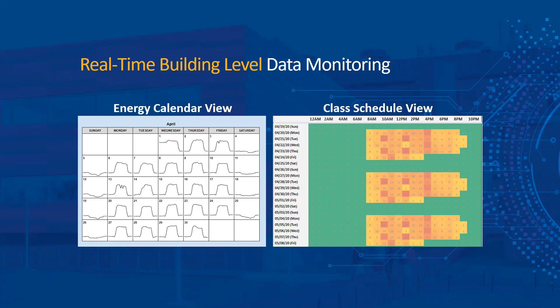So with all these buildings that we have in our system, it's almost impossible for 2 people to go through every single one every day. So what we did was we baselined the buildings. We said, hey, at 2 o'clock in the morning, you're supposed to consume roughly 30 kW. If we see a spike, if it goes above that threshold by a certain amount, we want to be notified right away. So we programmed that in there, and now if the building goes out of range—a lot of times our maintenance team might be working on it, they put things occupied 24/7 and then forget to put it back into place—we get these triggers right away and we say, hey, what's going on? I would talk to the HVAC department and then we would put things back to normal.